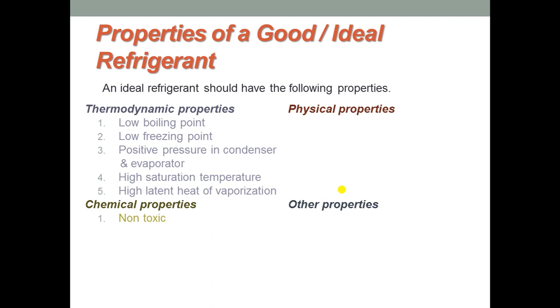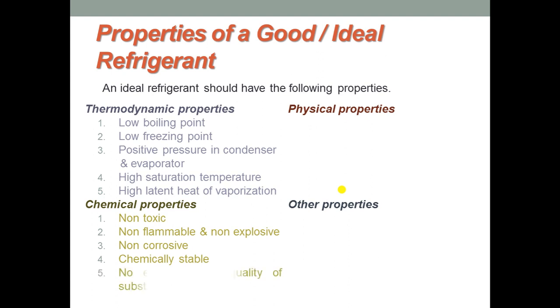Next are chemical properties. The first is non-toxic. The second is non-flammable and non-explosive to avoid risk of fire and explosion. Non-corrosive, so that the refrigerant does not corrode the machine components. Chemically stable, so that it does not dissociate or break down — the refrigerant has to be stable for the lifetime of the refrigerator. And no effect on the quality of substance stored, and non-irritating and odorless.